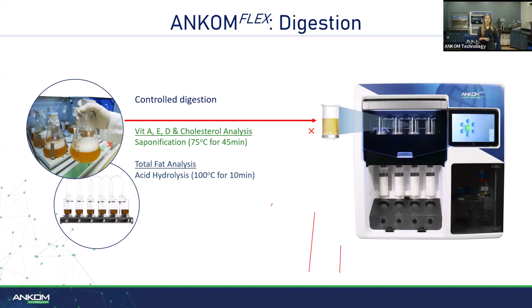The top portion that you're seeing is the digestion oven. That's where, for vitamin analysis, you'll do your saponification, or for total fat analysis, you'll do your acid hydrolysis. So this replaces those two very manual steps that your technicians would have to use a lot of glassware and a lot of time for. For the saponification, we do 75 degrees Celsius for 45 minutes, and for the acid hydrolysis, it's 100 degrees Celsius for 10 minutes.